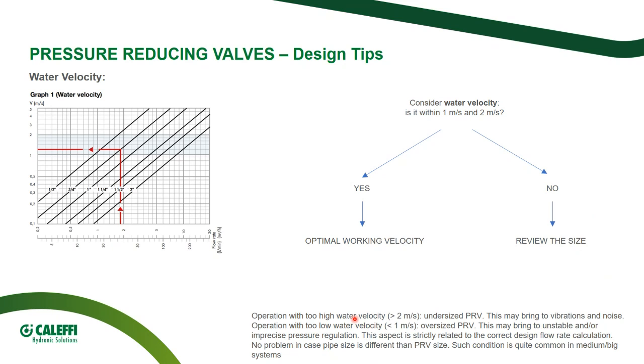Another tip, and we are almost done, consider water velocity. The optimal interval for water velocity in a domestic water system is stated between 1 and 2 meters per second. If the velocity is too low, I would have the risk of stagnation. But if it is higher than 2, I would have serious risk of noise, vibration, and damage to the valve. So if we are between 1 and 2 meters per second, no problem, it is optimum. If we have a different value, we recommend you to review the sizing.